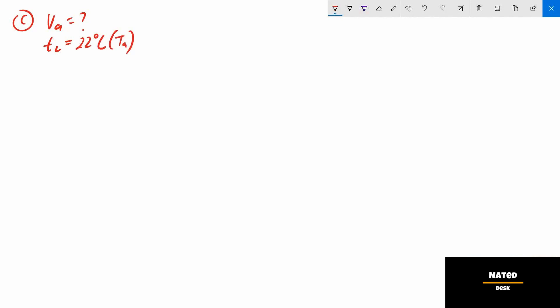Part C: calculate the air capacity of the air pump if air is cooled down to 22°C. The air capacity is va. The new tc is 22°C, which gives a new ta in Kelvin. Since we have a new tc, we need to calculate a new pa using Dalton's law: the absolute condenser pressure remains 9.997 kPa, equals ps at tc from the steam table plus pa.